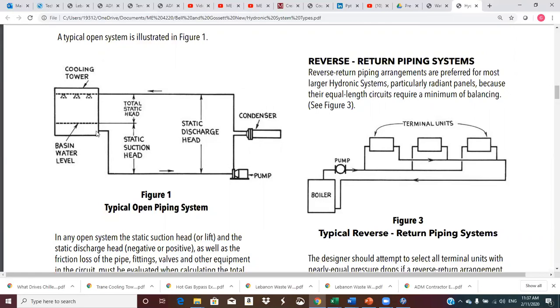Then the rest of the pump head is caused by friction. There's frictional loss. We have an entrance loss. We have piping losses. We have an elbow loss. We have more piping, another elbow, more piping. We come into the pump, come out of the pump. We have friction here, an elbow. We have the condenser pressure drop, all of this up to here. So the pump has to overcome, at whatever flow rate it's pushing, not only the static head, but the frictional head as well.